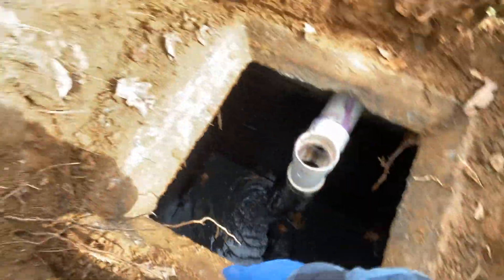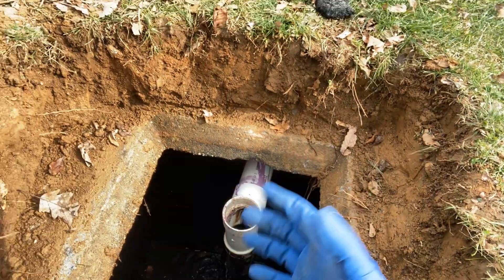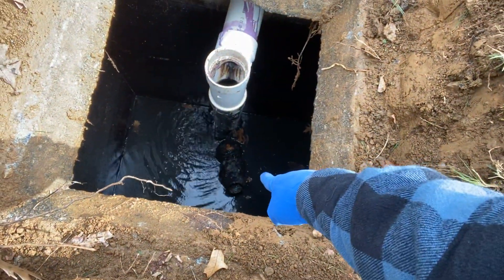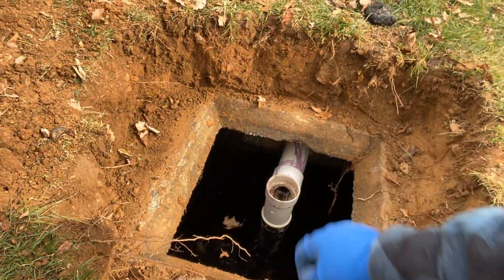The concrete is strong — make sure you pay attention to the thickness of that concrete. This tank is not that new, but it's newer than the one over there. It used to have a concrete inlet, and you can see it on the bottom down there. Whoever came in and did a repair installed PVC with a drop-down PVC as well.